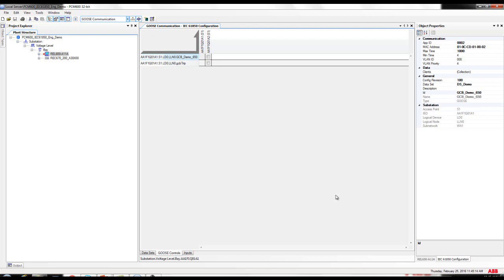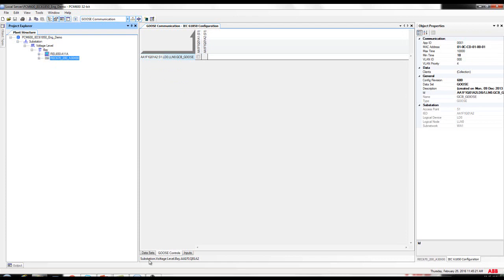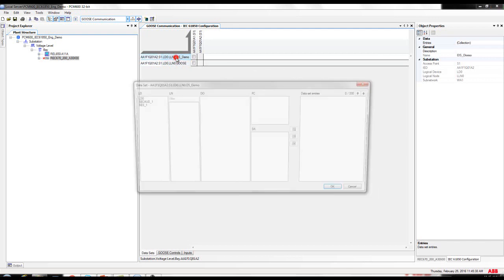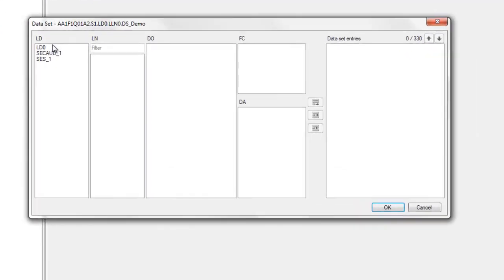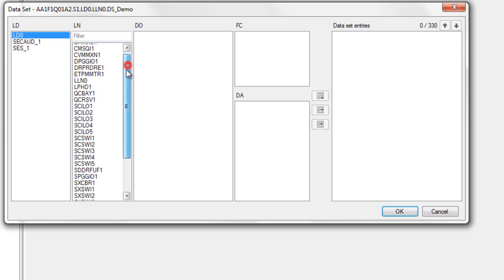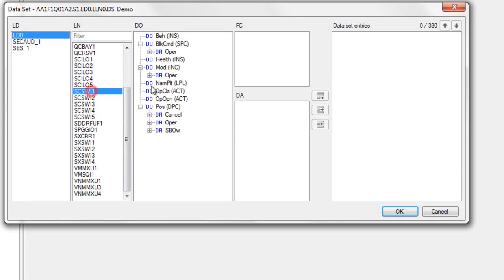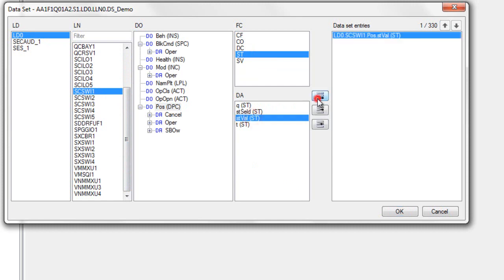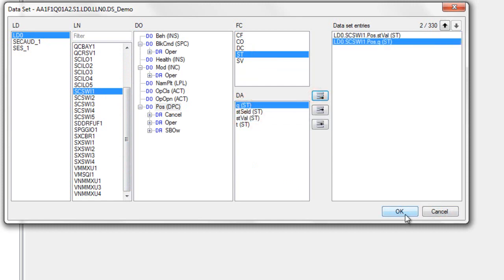Next is to configure the dataset and GOOSE control block for the REC670 relay. Select the REC670 relay, click on dataset, right-click, new, and label the dataset. Click OK. Double-click on the dataset to add the data attributes. The SCSWI1 is contained in logical device 0. Click and find the SCSWI1. Click on position — STVAL, add it, and the quality. Click OK.